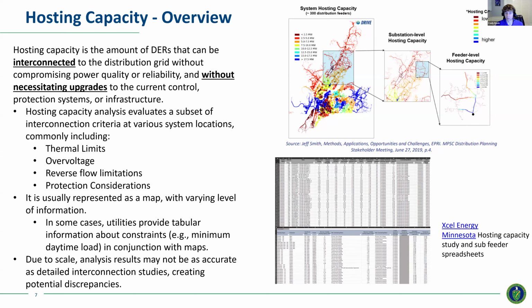There's value in providing some tabular information as well that can be used for different things. Generally, hosting capacity as a rule is an analysis of the entire distribution system, and it's generally required to be refreshed on a pretty regular basis. Because of the scale of what we're dealing with, you may not get as accurate a result as you would from an interconnection study, because in a detailed interconnection study an engineer does all the individual model prep and validation for every model. That does happen for hosting capacity too, but you're dealing with a much larger scale, so you may not get quite the same level - there may be automation going on that glosses over details a human would catch. So it's generally good, but it is a scale product, and that's worth keeping in mind.